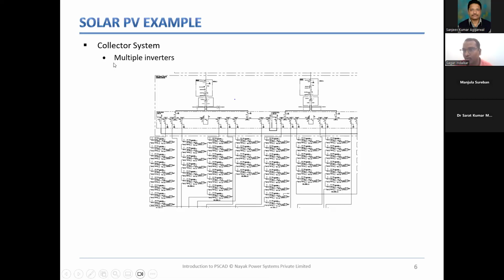But again, we are not going to model n number of inverters because it's very difficult to model hundreds of inverters in a simulation. Why? Because converters are switching based devices. They operate at very high switching frequencies. So to capture those switching frequencies, it forces us to use a very small time step, a very small sampling rate, so that the actual switching behavior is captured. So typically, if you use hundreds of inverters in the plant, then the simulation will take a very large amount of time to run without adding any actual benefit to the overall plant.